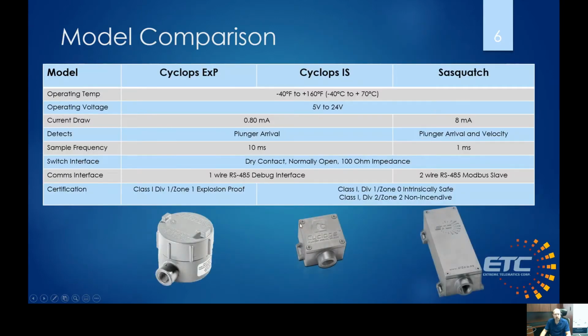So in terms of different models, we've got 2 different models of Cyclops. These are the same product, but they're certified differently. This one is obviously explosion proof or flame proof. That's the Cyclops EXP. The Cyclops IS is intrinsically safe. So both of them can be put into Div 1. The explosion proof can only go down into Zone 1, whereas the IS can go into Zone 0.